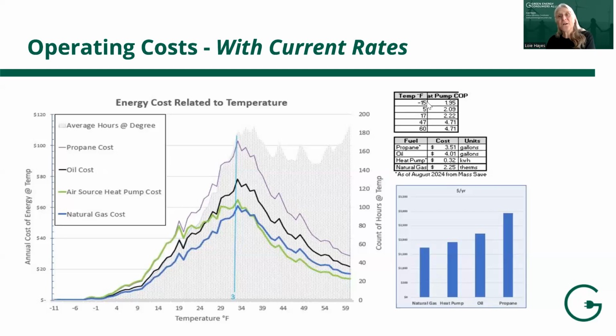I've also made clear this is the efficiency of the equipment that we've assumed for the air source heat pump. At 60 degrees, the coefficient of performance, COP, that's a measure of efficiency for heat pumps, is 4.71. That means for each 1 kilowatt of electricity you put into this particular heat pump, you're going to get 4.71 kilowatts of heat out of it. So it's a tremendously efficient system. That's why it's so cost effective at these higher temperatures. It's still that efficient at 47. At 17, it's dropped down to 2.22. At minus 15, it's at 1.95.